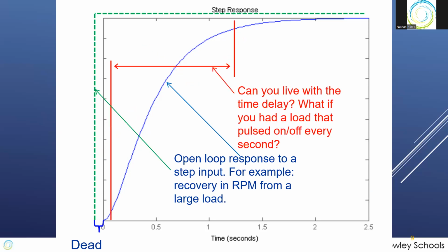But we have to ask ourselves, can we live with this time delay? What if we had this MRI load that goes bang, bang, bang, bang? Well, a lot of generators, when they first brought those on, would step down and recover. So you're at 60, you jump back to 59.6, and then you jump back to 59.2, and then back to 59, and then next is 58.7, and you just find yourself dropping off because you never really fully recovered from those impacts. So in that case, you could not live with that time delay. You'd have to do something to make it respond quicker than that. Otherwise, you'll just hammer it into the ground. So, a large load step input.